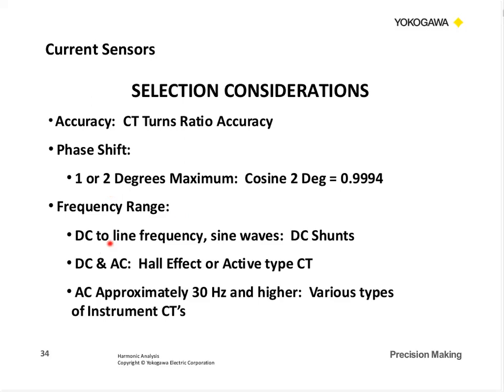Frequency range is very important when we're talking about distorted waveforms. And shunts, that's why I say these are good to line frequency, a few hundred hertz. Typically, be careful on any type of distorted waveform. Then we have the Hall effect type CTs, transformers, that will measure DC and AC. With the Hall effect device, you do lose some accuracy just because of the technology. And the active type, like the Yokogawa LEM CT, very accurate and very good for distorted waveforms. And then your standard instrument transformers. These are good typically from about 30 hertz and higher, like ours, from about 30 hertz to 3,000 hertz. There's various types of these instrument transformers around, but look at their specs very carefully. Some will work, and the others you have to be careful of.